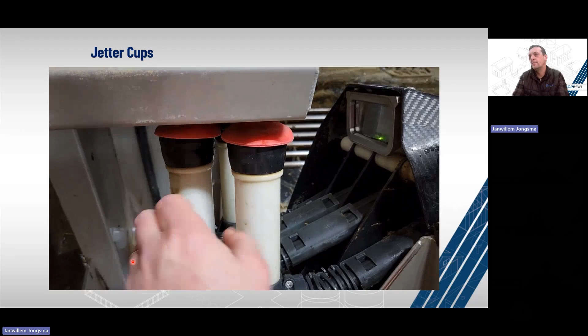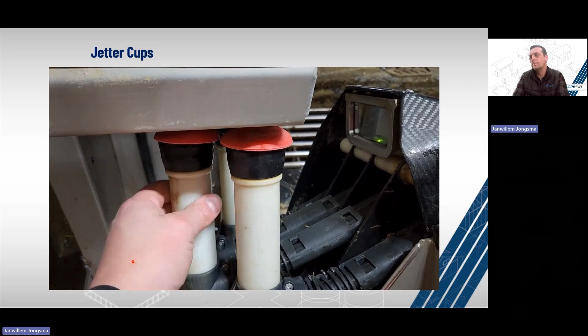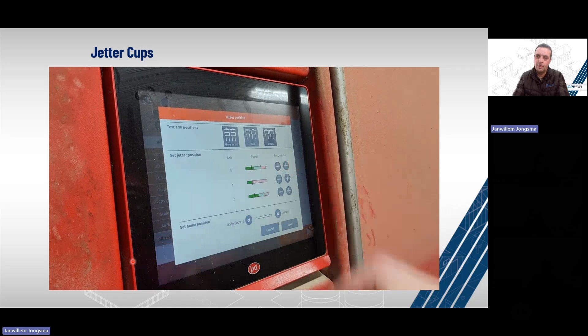Next, we're having the jetter cups. Getting the cleaning not okay for a specific quarter alarm. That can be that the jetter calibration is off. As you can see here, the rear cup is loose compared to the front. So it can suck in air during a main wash. So here we're doing the calibration procedure. It's under the calibrations. You can calibrate the jetter position and look after calibration. Now it's tight again under the jetters.